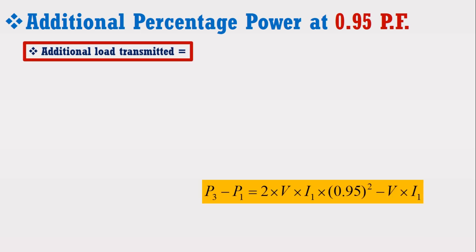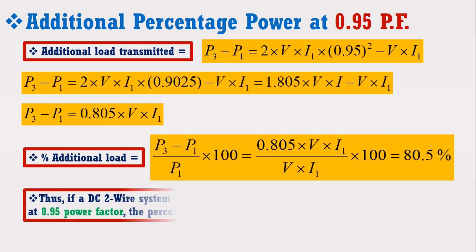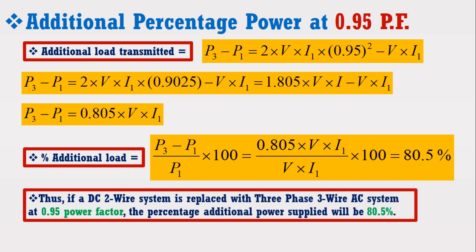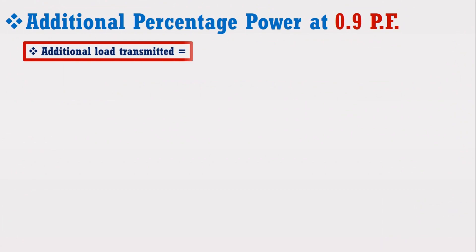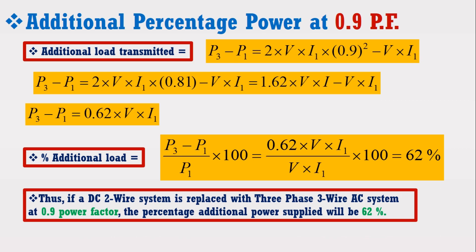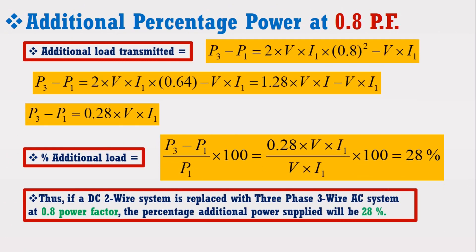Now I am going to calculate percentage additional power at 0.95 power factor. By putting the power factor value in the expression, it is observed that when a DC 2-wire system is replaced with a 3-phase 3-wire AC system at 0.95 power factor, the percentage additional power supplied will be 80.5%. Similarly, the percentage additional power supplied at 0.9 power factor will be 62%, and at 0.85 power factor will be 44.5%, whereas at 0.8 power factor, this percentage additional power supplied will be 28% only.